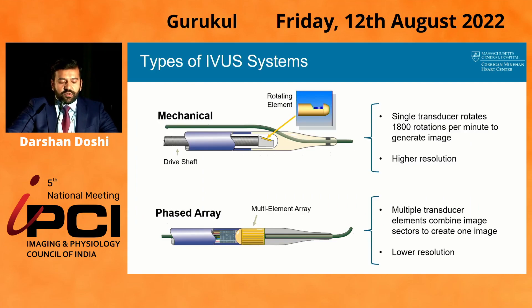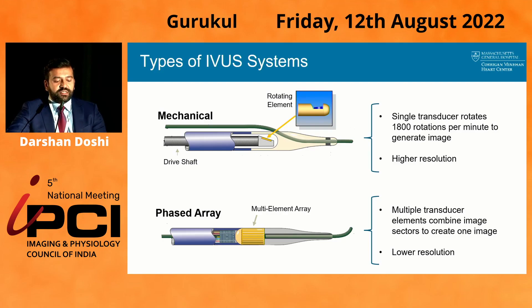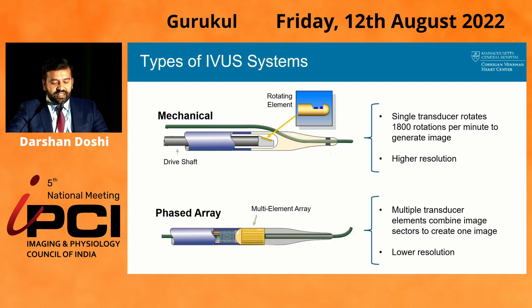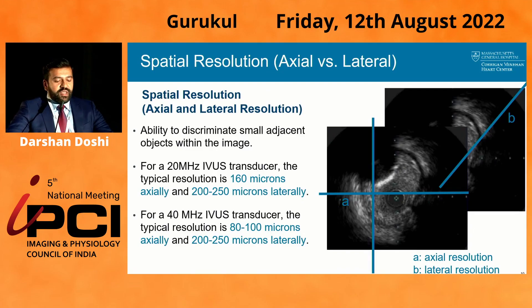The mechanical or rotational IVUS system allows for higher-frequency imaging. It uses a single transducer rotating at approximately 1,800 rotations per minute to generate the image. Because of the higher frequency, it achieves much better resolution. The phased array, or plug-and-play IVUS, uses multiple transducer elements that each take a sector of the vessel, fired sequentially so it appears to rotate — but because of how that's done, you get a lower resolution.